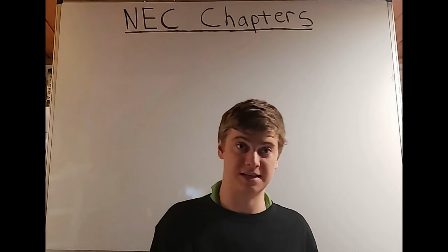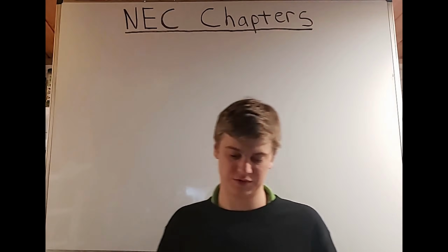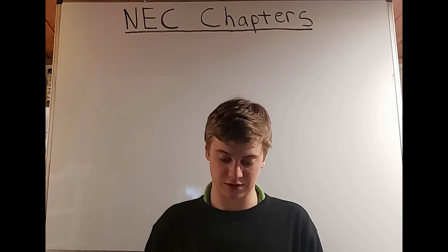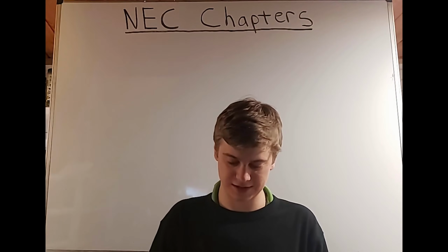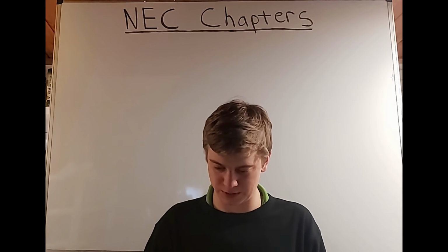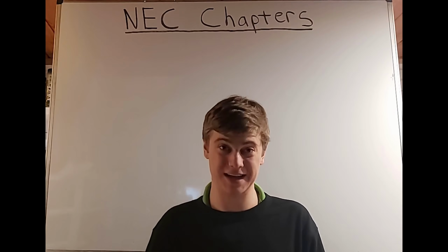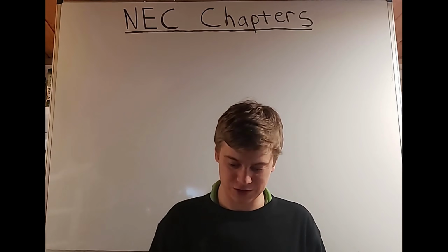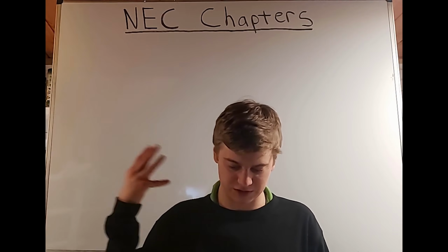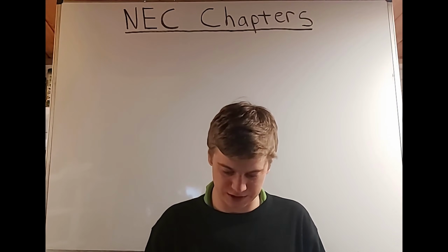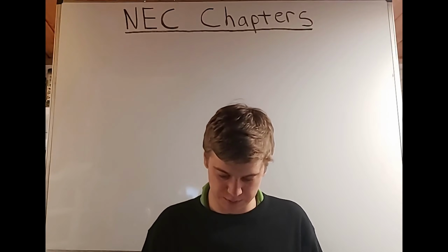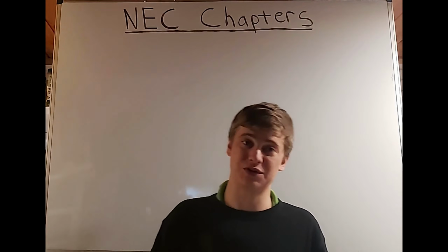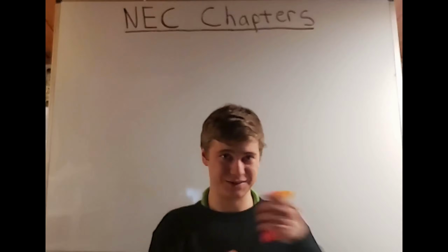I chose EMT because that's the first one, but you're going to want to go back on the first page and see that it tells you a table and page. So it tells you where all these are listed on each page. Make sure to use this, because as you see, some of them are separated by a pretty big number. It starts on page 730, it ends on page 814. So you're not going to want to flip almost 100 pages trying to find what you're looking for. You're going to want to go to this front page. If you have EMT, you see that's page 730. But if, let's say, you have PVC Schedule 40, then you're on page 794. Okay, so that's over 60 pages after it. You're not going to want to flip through all that.